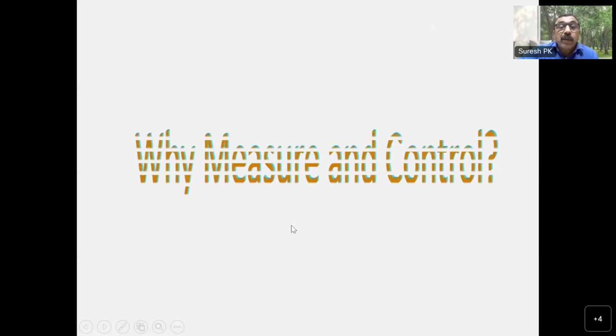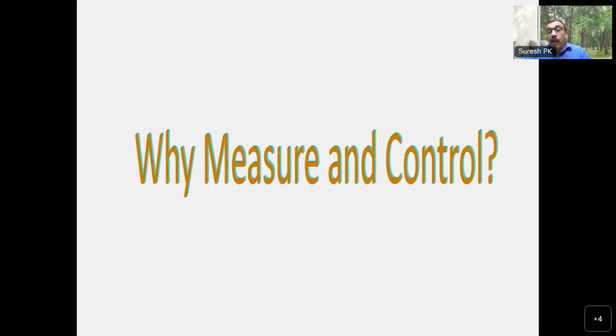I am trying to give you a brief on flow meters, the characteristics of flow meters, the calibration of flow meters, and the uncertainties involved in that calibration. Measurement and control is a must in modern industry, especially when you are using automation and artificial intelligence. Measurement and control is the most important factor of any industry to maintain quality, to maintain profit, and to ensure the consumer is satisfied with what is being measured.